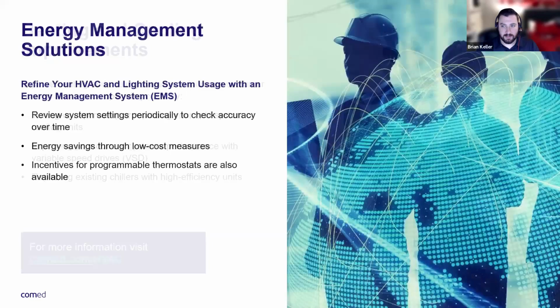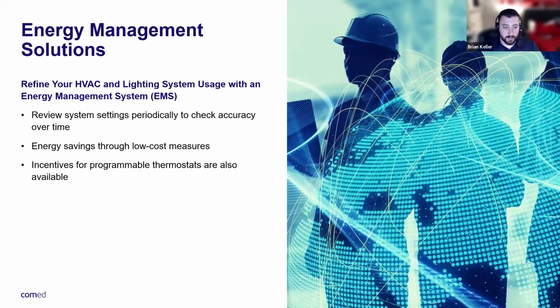Now, our energy management solutions. Improving your energy management system starts with reviewing system settings periodically, since a lot can change in your building. Making sure there's a periodic check to confirm all settings are accurate and fully serving your building's needs. You can also experience additional energy savings through measures like fine-tuning your scheduling, optimal start-stop of air handling systems, resetting air supply temperatures, and resetting chilled water temperatures. Keeping all of these finer details in mind shows how simple adjustments can have a big impact and big savings.